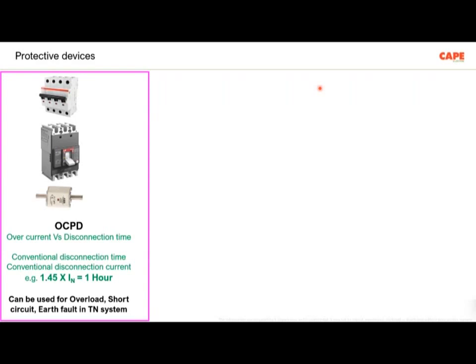Now, once you select this protective device, of course, the current rating, there are several measures. For example, if you select an MCB, what is the load requirement? Then the sizing of the conductor shall be calculated based on the load requirement. The sizing of the MCB has to be calculated based on the size of the wire and so on. I'm not going into it, but you always should keep in mind that there is a parameter called conventional disconnection time and conventional disconnection current. What it means is the conventional disconnection current is 1.45 times the rated current of that particular protective device. Say, for example, you have a 10 amps MCB. This 10 amps MCB can take a time of up to 1 hour to trip if the current is lesser than 1.45 times.